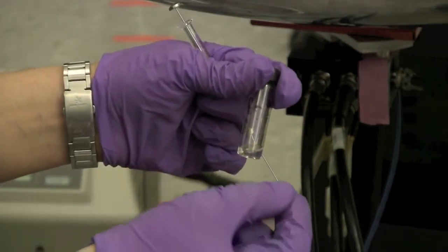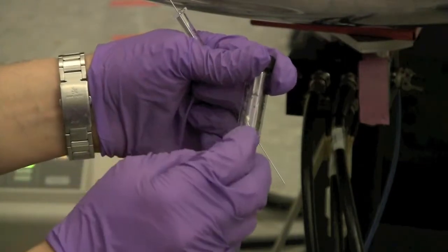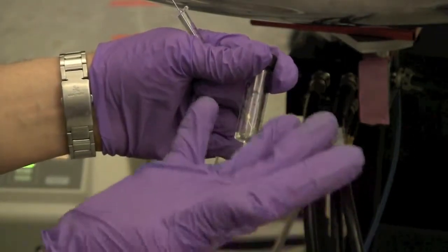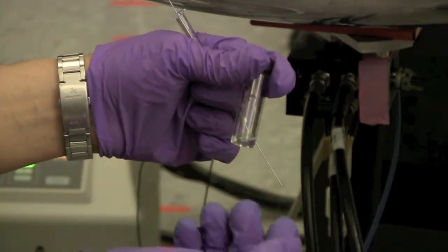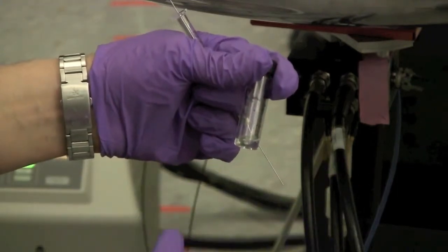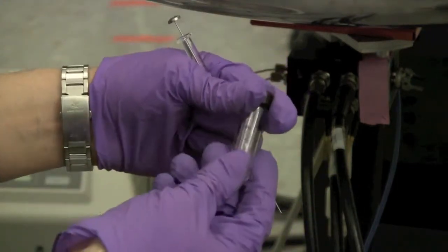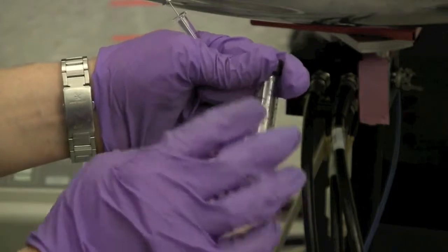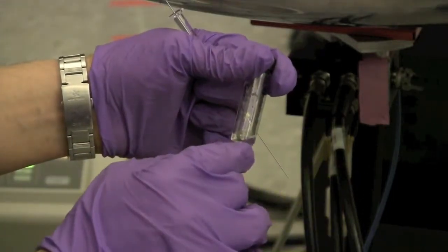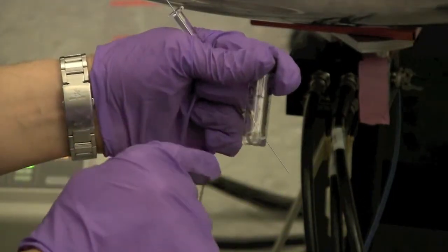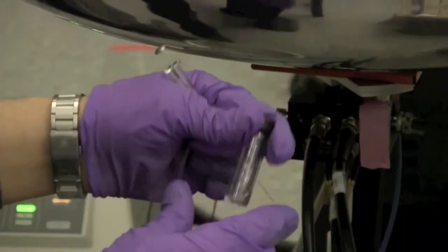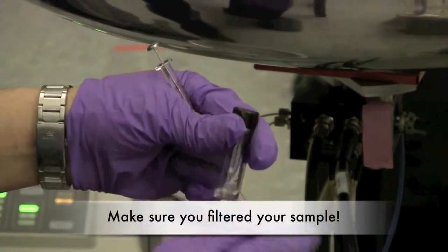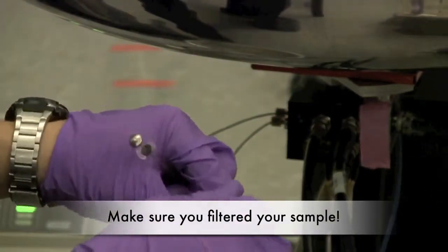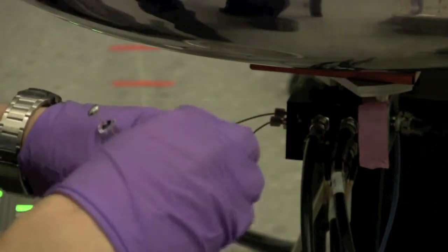But just remember that if you've concentrated it down, there's a possibility that it is precipitating, and that even though it's clean, if it's precipitating, that could clog the probe. So we want to make sure that there's no particulates in the sample at all, even ones that you can't see. Just because it's clear to the eye doesn't mean that it's clean enough for the probe. It could still contaminate or clog the probe. So this sample has been filtered. I'm going to go ahead and load it in.